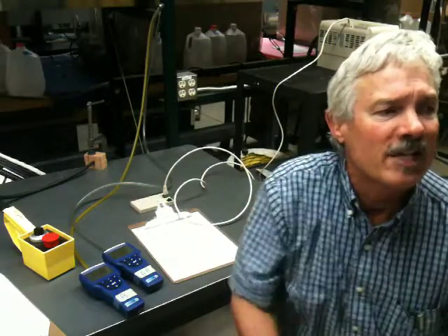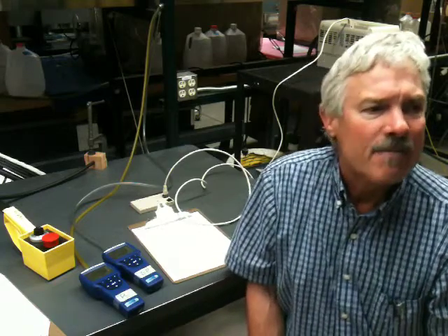And then in your analysis, you will compare the electrical power consumption to the aerodynamic power of the airflow, and from that you can determine the efficiency. What we generally find in our lab is that the fans operate at nearly a constant electrical power, and so the efficiency increases as the aerodynamic power increases, and we will discuss that in more detail later.